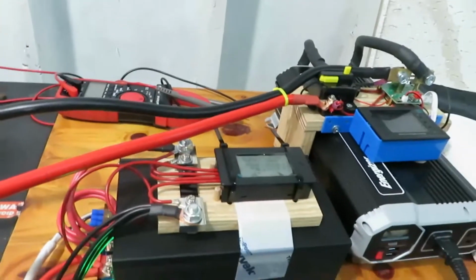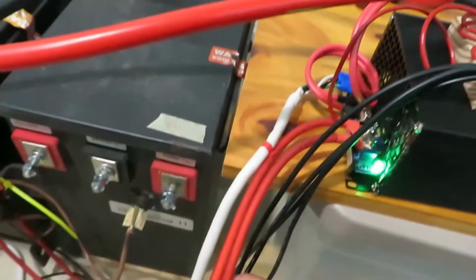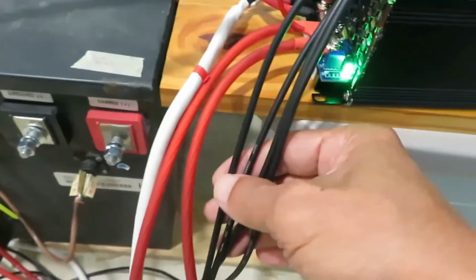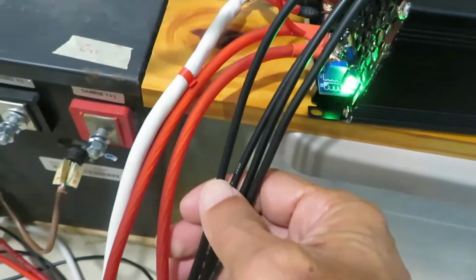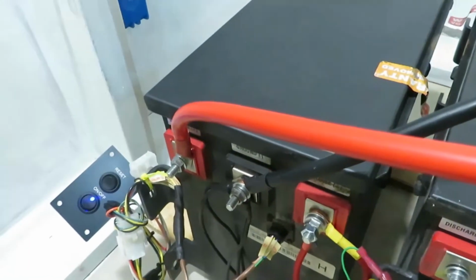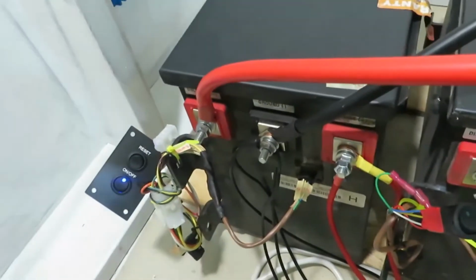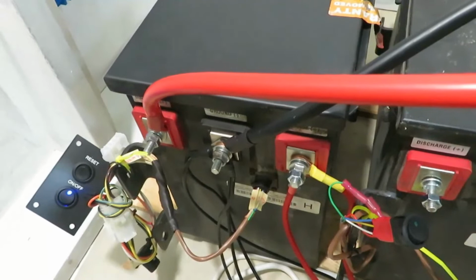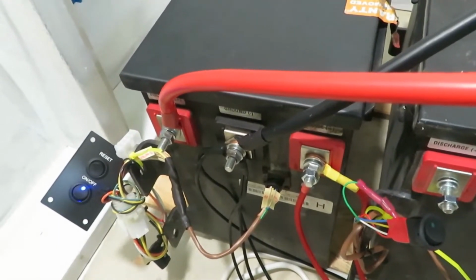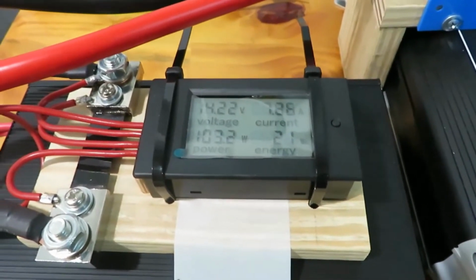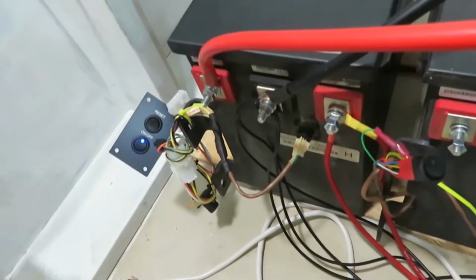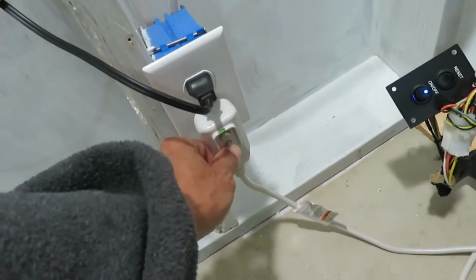Since the charger is capable of about 60 amps, I have 2 of the number 8 cable in parallel going to the charge side, and for the negative side, I have 4 of the 12 gauge wire in parallel going to ground. So instead of waiting, okay, I hear a little small clunk, a small click by a driver. So we should be able to hear the big clunk soon. And oh, actually it's already closed because we are charging right now at 7 amps. So the charge side is already closed because I put the covers on and did not hear the clunk very loud. So I'm going to turn off the charger.